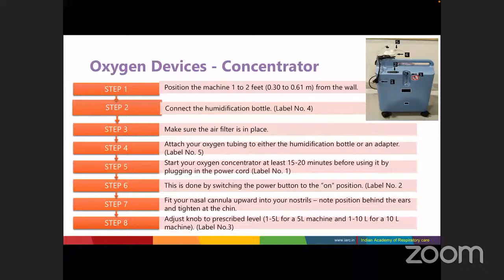Second, fit your nasal cannula upward into your nostrils. Position it behind the ears and tighten under the chin. After that, adjust the knob to the prescribed oxygen level. If it is a 5-liter concentrator, you can adjust from 1 to 5 liters, and if it is a 10-liter one, then you can adjust from 1 to 10 liters. But before using it, please contact your healthcare provider.